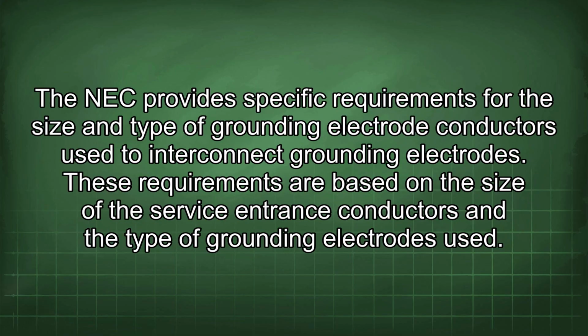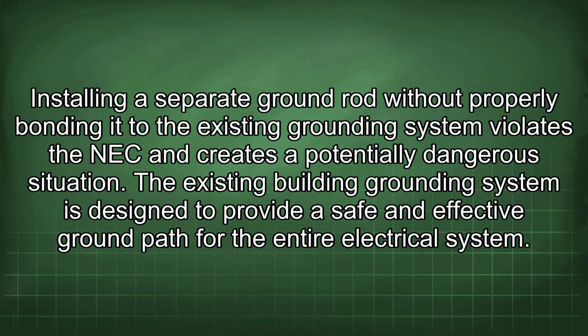The NEC provides specific requirements for the size and type of grounding electrode conductors used to interconnect grounding electrodes. These requirements are based on the size of the service entrance conductors and the type of grounding electrodes used. Installing a separate ground rod without properly bonding it to the existing grounding system violates the NEC and creates a potentially dangerous situation. The existing building grounding system is designed to provide a safe and effective ground path for the entire electrical system.